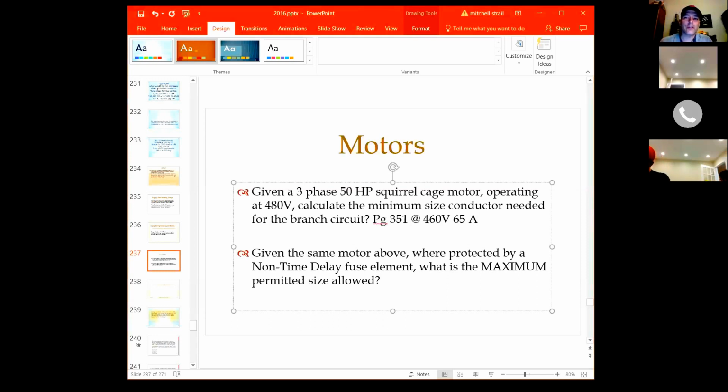And then for the conductor size, what multiplier did you use for that? The size is number 6. I told you 4, but 6. Well, what did you do with that 65 amps? Did you multiply it times something first? I need to multiply it by 125%, right? 125%, that's right, because that motor is going to be considered a continuous duty application.